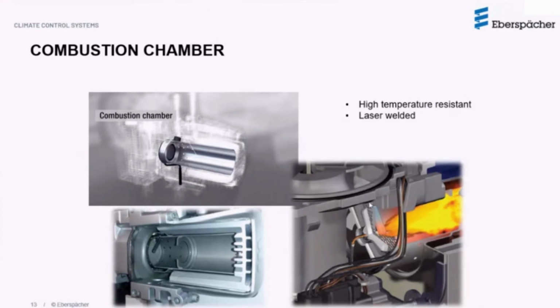The evaporative mat assists with the vaporization of the fuel. This is not a removable part, so you cannot just remove the mat and replace it with a new one — in the unlikely event you have to replace a combustion chamber, the entire combustion chamber needs to be replaced. But once again, in the last 4 or 5 years, we haven't seen any complaints leading to such major repairs in the field, which is definitely encouraging.